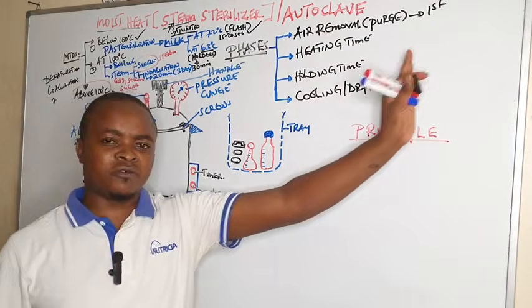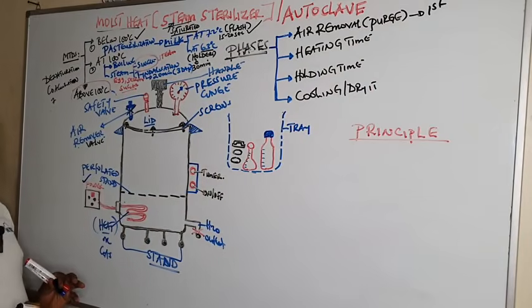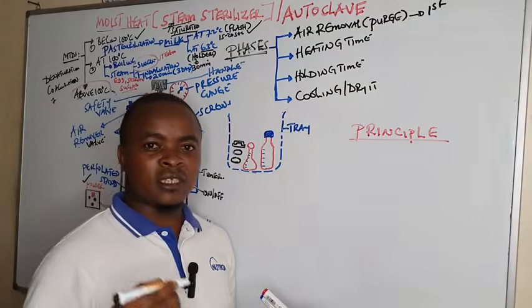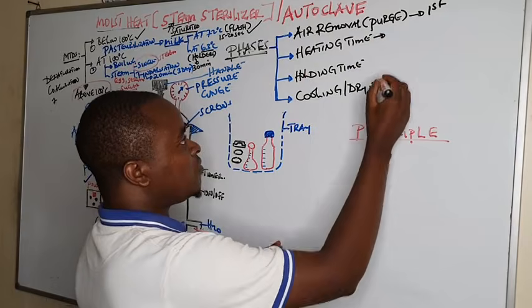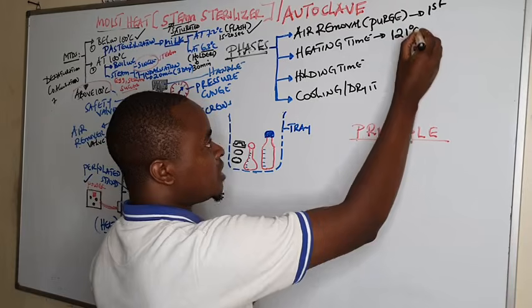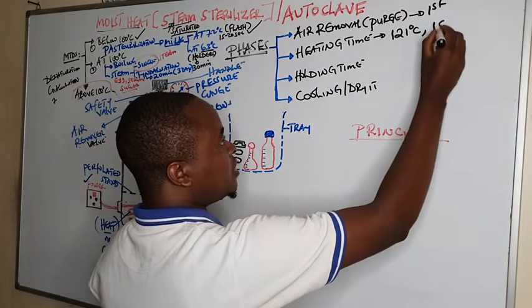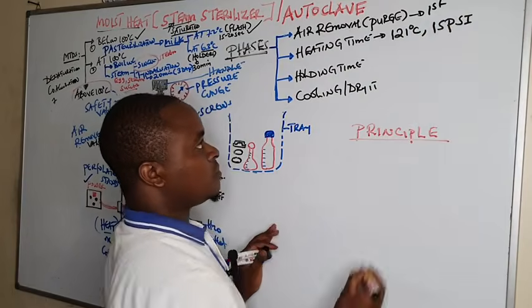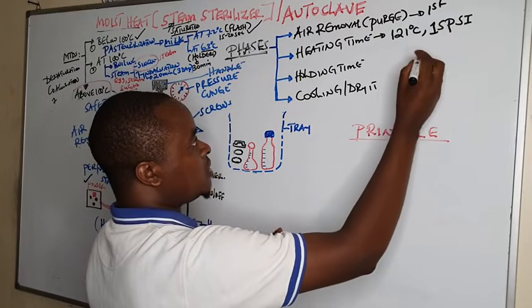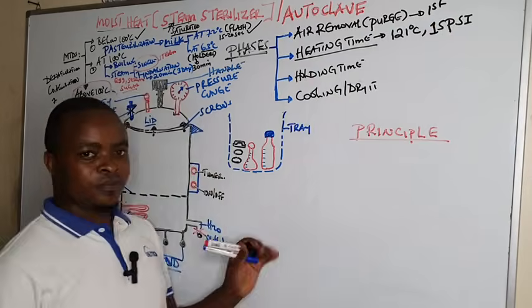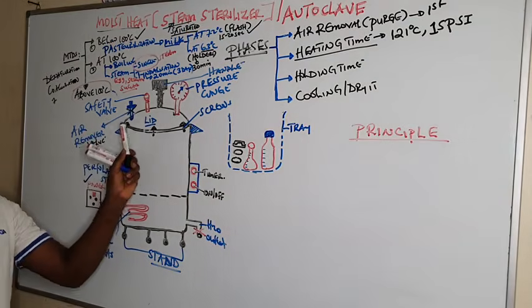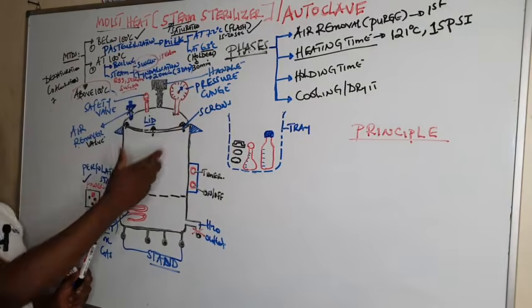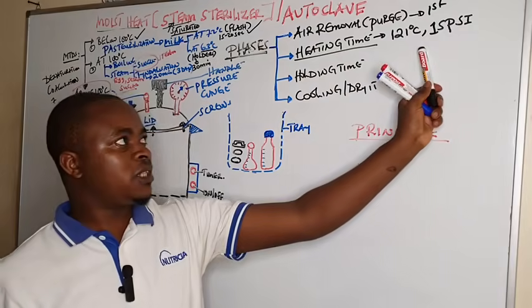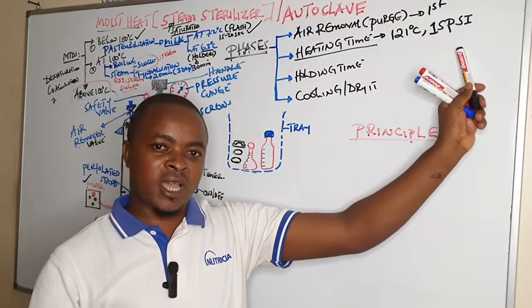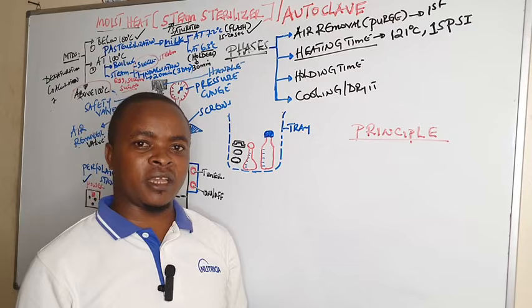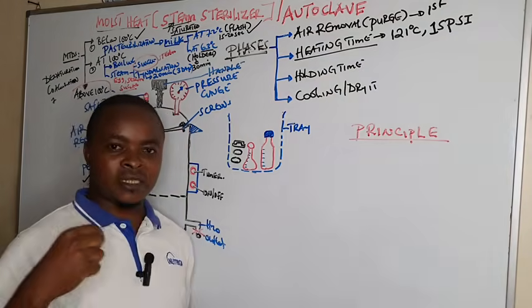Then when all air is removed, we close the air remover and heating time begins. Heating time is the time taken for the autoclave to achieve a temperature of 121 degrees centigrade at a pressure of 15 pounds per square inch. That is the pressure we use. After closing the air remover valve, the temperature at the gauge begins to rise, and the pressure. When it reaches 121 degrees centigrade at 15 pounds per square inch, the time taken to achieve this so that sterilization can start is what we call heating time.